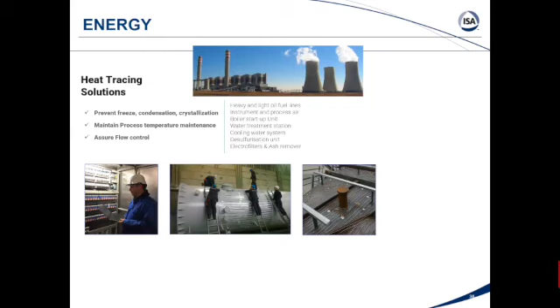Most commonly our applications are 40 degrees maintain or freeze protection, but there are numerous applications where, for example, we're doing some things with DuPont right now, and the maintain temperature for their piping and vessels is around 600 degrees Fahrenheit. So those are temperatures we can maintain easily. The highest maintained temperature I've gotten into was around 1200 degrees Fahrenheit with heating cables. So it's not just a freeze protection cable, which is what everyone's mostly familiar with — we can maintain vessels, equipment, and piping well above that temperature as well.